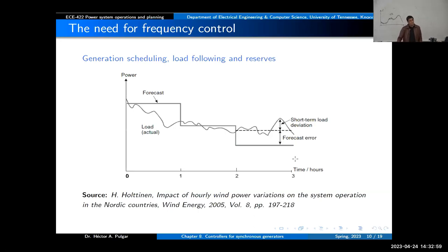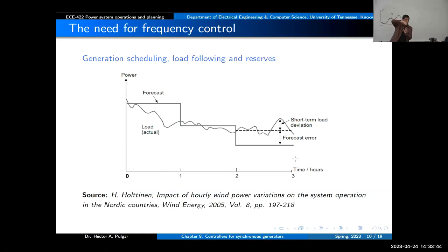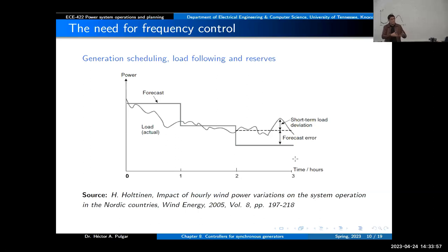The term governor refers to controlling power or frequency in the generator. For a hydro generator, you take a measurement of frequency — if it's 60 hertz, you do nothing, but if the frequency goes down, you need to increase the power. You process that with a controller and obtain a signal that gives the order to the valve to open more, letting more water go to the turbine and producing more power. That loop is basically the governor. The same action applies to a steam power plant: open the valve to let more steam go to the turbine and produce more power.